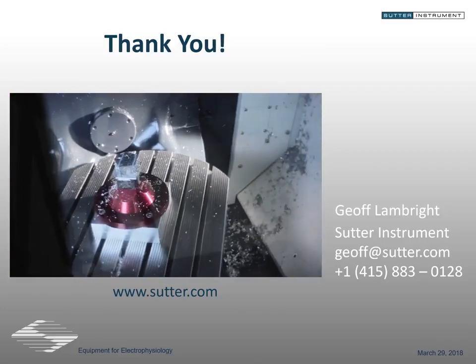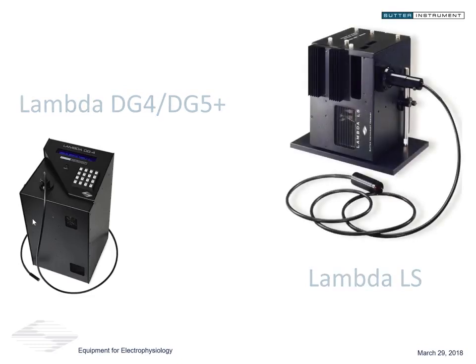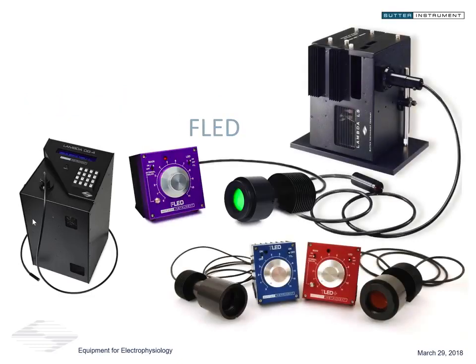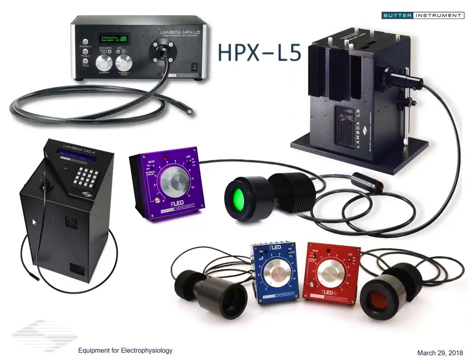So we do have a couple of questions, so let's start off. Here's a question regarding the LEDs. In the age of LEDs, is there still a reason to use a conventional light source? Yes, but that argument is becoming harder and harder to make every day. Is there any particular applications where... I can think of some right off the bat where, for example, more than 4 channels of excitation might be needed, in which case you would be better served by a xenon light source and potentially a high-speed filter wheel, for example, that could open up to maybe 10 different excitation wavelengths as opposed to being limited by 4. So that's a potential application area where one might still turn towards the xenon lamps, for example.